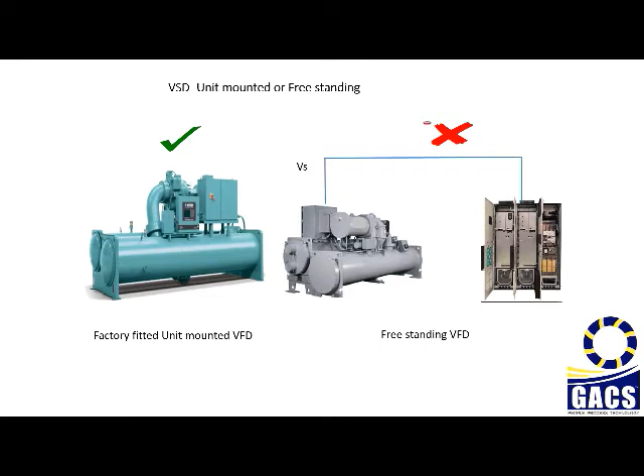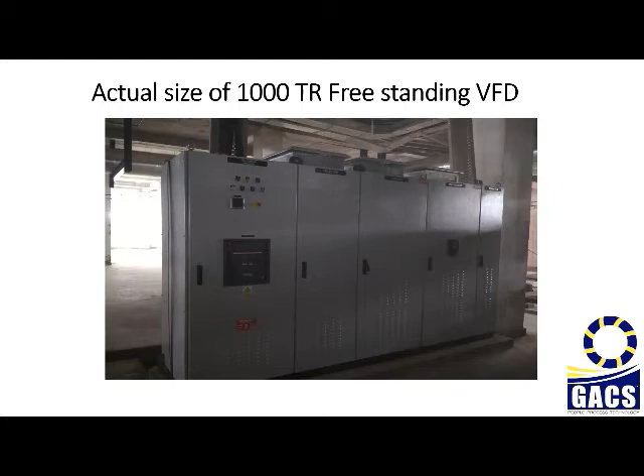So you can see this slide. This is a 1000 TR machine with a freestanding VFD. You can see the size. The size is too large. There are 3 compartments for cooling purposes. This kind of VFD has a lot of electrical components in it. If one of those components fails, the complete VFD will shut down, the complete chiller will shut down, and your operation will stop. So this is a complex system, and this is an air cooled VFD, and the size is very large. Accordingly, the heat dissipation through this VFD is also very high, which increases the overall plant room temperature and creates ventilation issues or increases the power consumption on the motors. It can also lead to overheating of the pump motors, maybe the chiller motor. So those kinds of issues can be there.